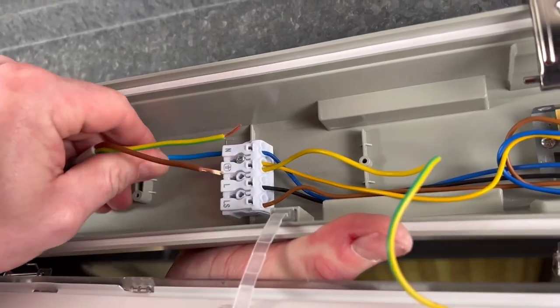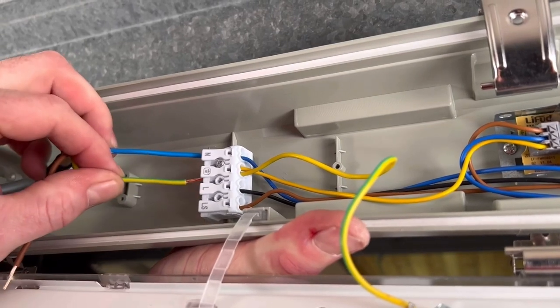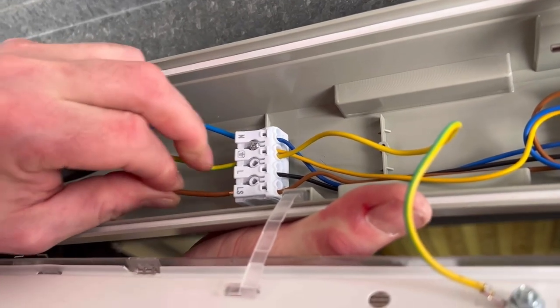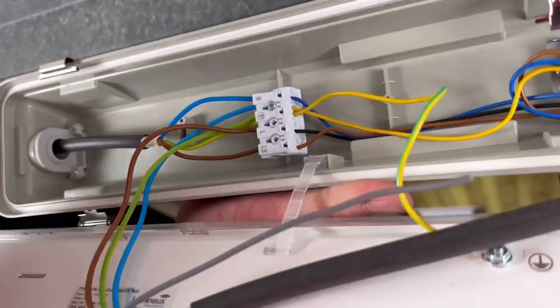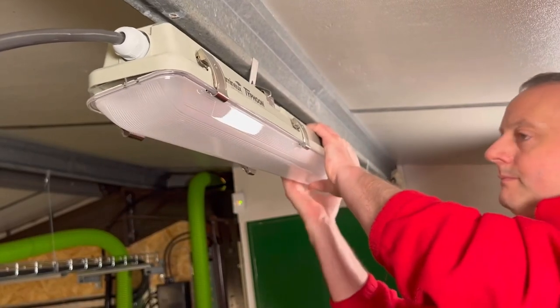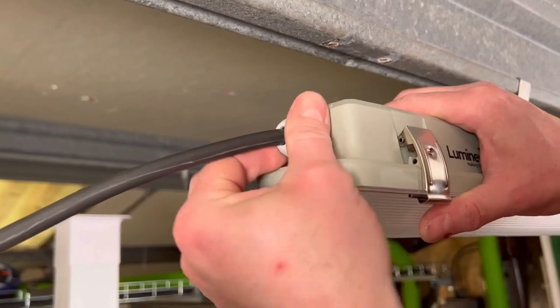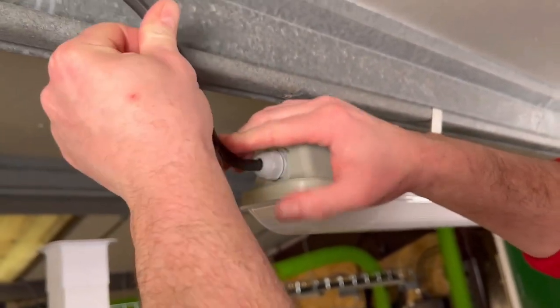I'm going to continue the feed on to the next one. This time, I'm not going to take a permanent line through — though normally you would carry that permanent line connection through in case you've got several fittings with every third one being an emergency fitting. I've only got one more fitting to go to, so I'm going to use a standard three-core cable to make those connections. And then that's it really — it's nicely, easily connected by coming in each end of the fitting. I can now put my cover on and use those clips to hold it back into place before energising the circuit.